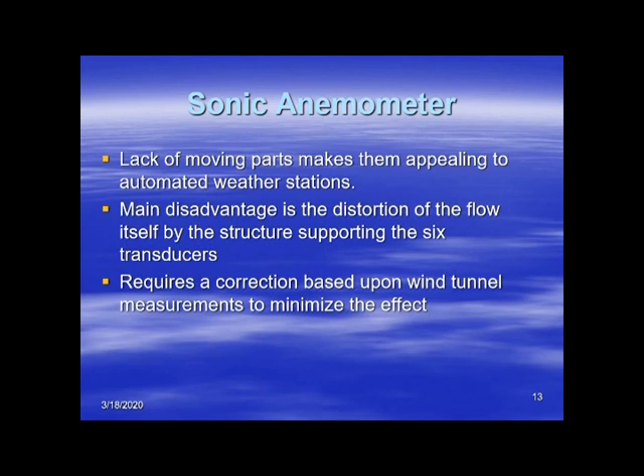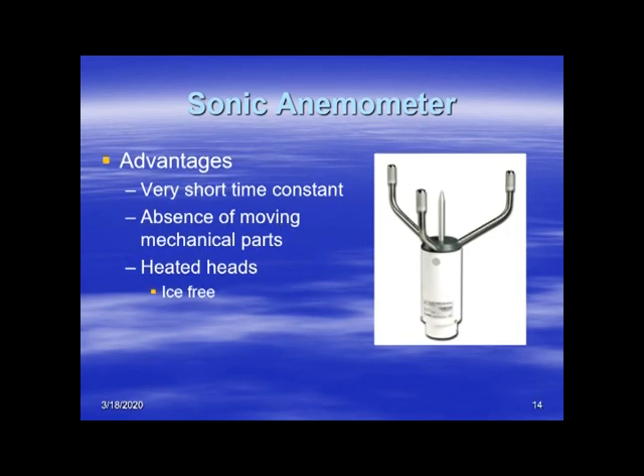To summarize, the advantages are a very short time or distance constant, no moving parts, and these heads are typically heated so that you have ice-free wind measurements — which was a problem with cup anemometers, which would fill up with snow and ice and degrade the wind measurements.